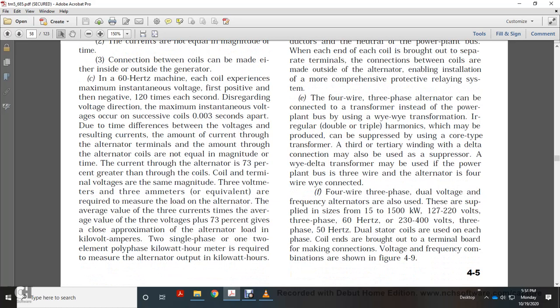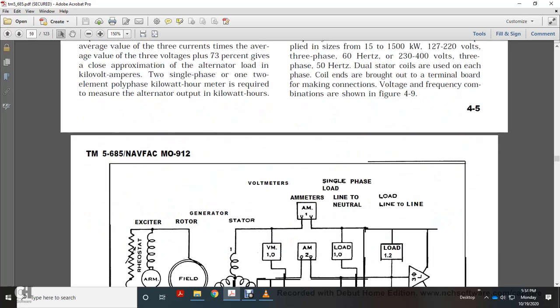The 4-wire, 3-phase, dual voltage frequency alternator is supplied in sizes of 15 to 1500 kilowatt: 127 to 220 volt, 3-phase, 60 hertz, and 230 to 400 volts, 3-phase, 50 hertz. It has dual stator coils, with each phase coil's ends brought down to the terminal board, making the voltage frequency connection combinations shown in figure 4.9.